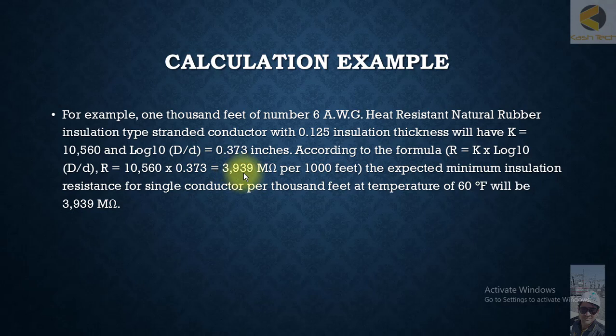So expected minimum insulation resistance for single conductor per thousand feet at temperature of 60 degrees Fahrenheit will be 3,939 megaohms. So this is one of the ways where you can find out the acceptance criteria for a given cable. Thank you very much.